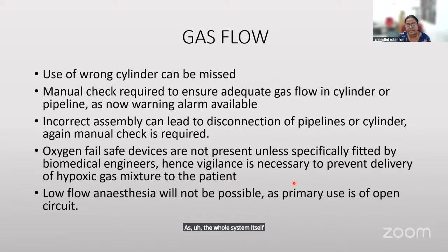There is no warning system available as there is in the modern anesthesia workstation. If there is incorrect assembly, it can lead to disconnection of the pipelines, and again a manual check is required for the same. Older machines do not have any oxygen fail-safe devices, such as the manual whistles which were introduced later on. Low flow anesthesia is also not possible in the basic Boyle's machine, as the whole system itself is designed against that possibility.